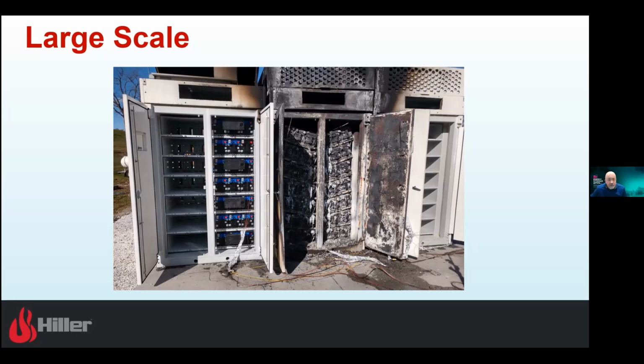I'll throw this to PNNL now. One thing you and I are looking at is what happens if we open the doors—does that prevent gases from building up so they escape? What I'd say is we're probably going to move it back to a fire condition again. Even if we open those doors, we've got oxygen going in there, and we're probably going to catch fire. So maybe there's a combination of opening the front and opening the top that might provide some benefit going down the road.